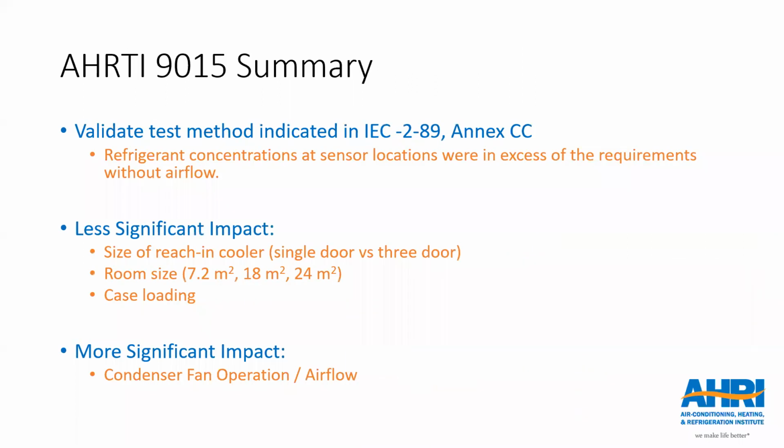So with this test, we were able to validate that the test method in IEC 2-89 Annex CC did have the effect of showing that there were refrigerant concentrations when the door was opened. The big takeaway from this for me was that the refrigerant concentrations at those required sensor locations were in excess of the requirements in the standard with the exception of that airflow.